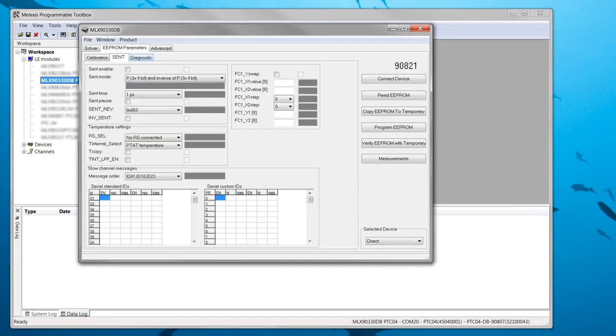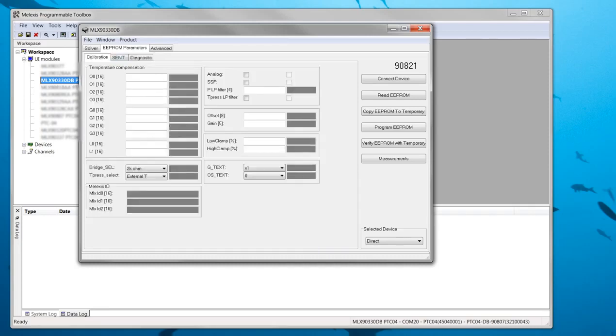The parameters in the Calibration tab all relate to the calibration or output in some way. For example, the digital compensation parameters at the top left, which together form the offset, gain and non-linearity compensation of the pressure signal. These parameters are set during calibration and are responsible for the output transfer curve. On the bottom, the three Melexis IDs are also visible. The combination of these IDs is unique for each device.